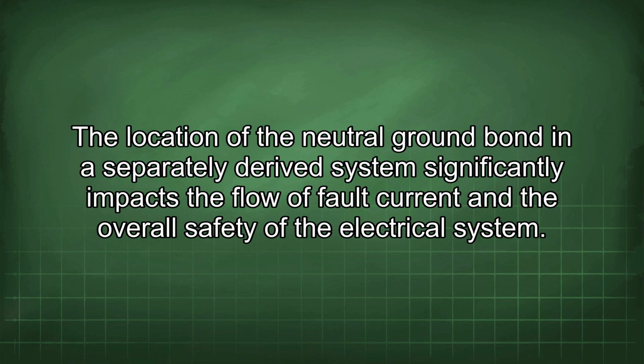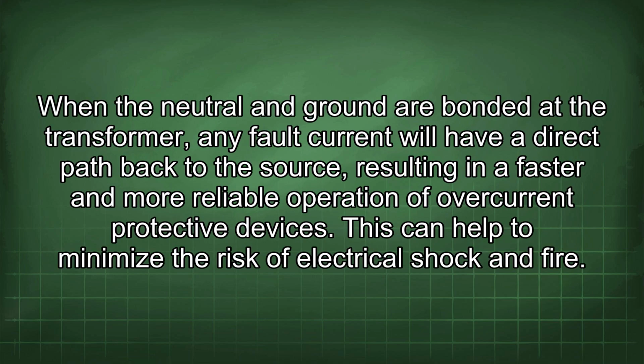The location of the neutral ground bond in a separately derived system significantly impacts the flow of fault current and the overall safety of the electrical system. When the neutral and ground are bonded at the transformer, any fault current will have a direct path back to the source, resulting in a faster and more reliable operation of overcurrent protective devices. This can help to minimize the risk of electrical shock and fire.